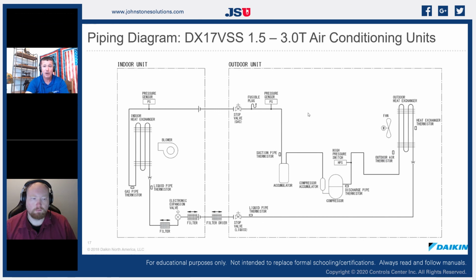If I get an error code on my diagnostics that says I'm having an issue with my outdoor air thermistor, I can look at my piping chart and go, oh, it should be right there by the condenser coil. Or if I got an error for my liquid pipe thermistor, oh, I better go out there and look close to my service valve, right? If I got an error code on my indoor unit for a gas pipe thermistor, well, there it is. Here's my expansion valve, so it's after my expansion valve. It's not the first one, because the first one's the liquid pipe, so it must be the one on the outlet of the coil. It's the one that's helping read superheat.